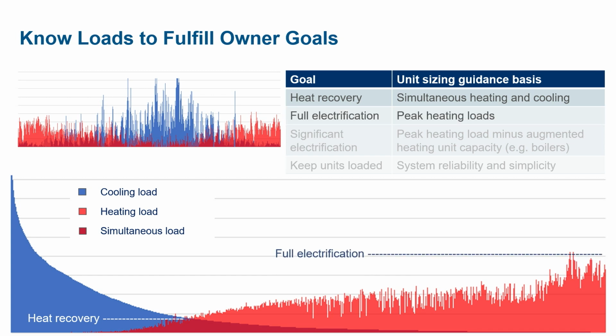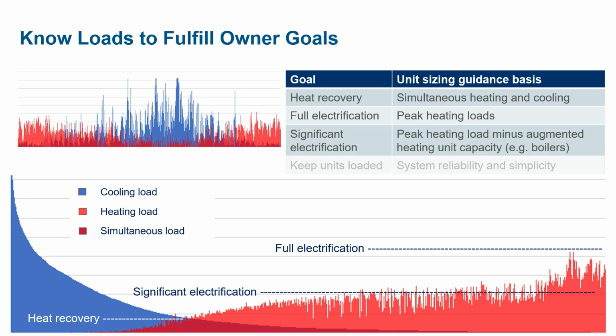If the goal is full heating electrification, then the units must be sized to satisfy the peak heat load. But maybe in some areas, it's okay to handle most of the heat load with a smaller boiler acting as a peaker unit like we saw earlier. This may provide more heating options: electric or fossil fuel boilers, heat pump water heaters, renewable natural gas, to name a few, satisfying those extreme loads.